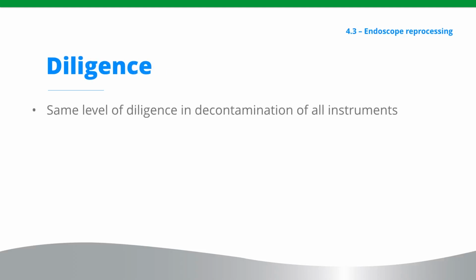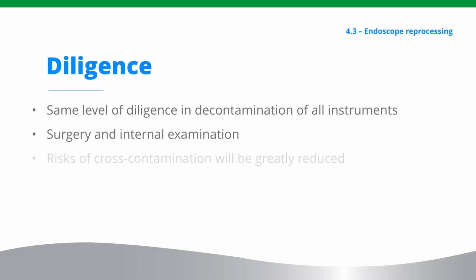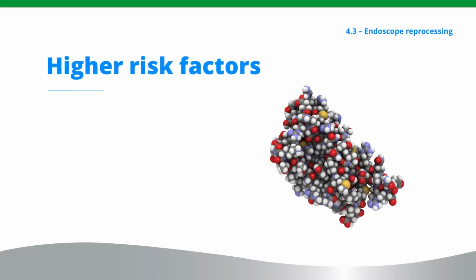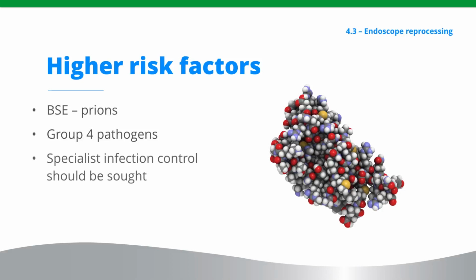If the same level of diligence is exercised in the decontamination of all instruments used in surgery and internal examination, the risks of cross-contamination will be greatly reduced. Some organisms pose higher risk factors than those more often found in practice. Bovine spongiform encephalopathy is caused by prions. These organisms are extremely resistant and a very special sterilization process must be engaged. Another major risk would be any patient suffering a Group 4 condition. Thankfully, the likelihood of encountering BSE and Group 4 conditions is rare, but if it does occur, then specialist infection control consultancy should be sought.